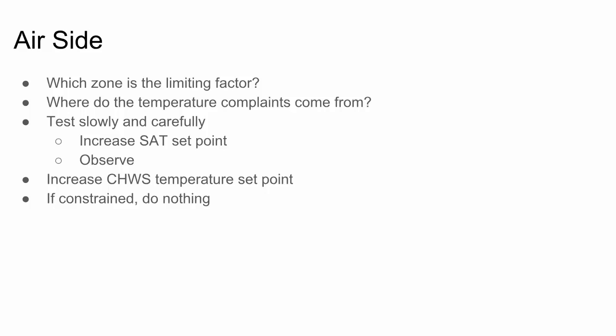If, on the other hand, we find that all zones can tolerate some increase in chilled water supply temperature, then we're going to make that small increase, maybe just half a degree or one degree. And then we'll observe again. We'll watch. We'll look at trends. We'll take a few weeks to walk the floor and see how things are going, see how many temperature calls are coming in. And if it's successful, we may want to push that up a bit more. And that's a continuous incremental process that operators should be looking at all the time.